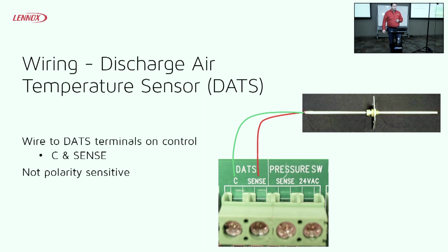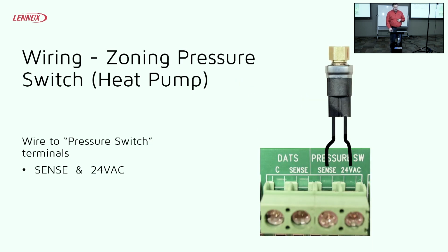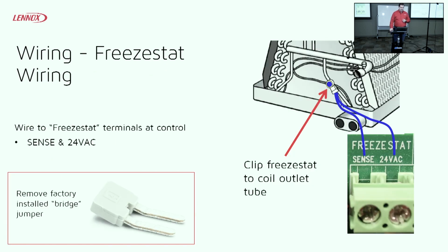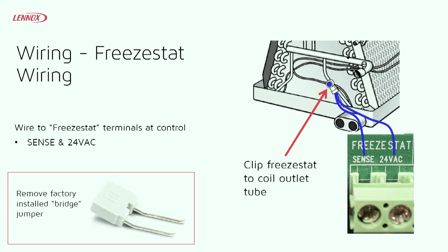Discharge air temperature sensor, again, just wire straight to the zone board. It's just a basic thermistor, so it doesn't matter. You can switch those wires any way you want. Heat pump pressure switch, again, that's going to wire back to that zone board with the pressure SW terminals. And then your freezestat will have this little bridge installed there from the factory. So if you do end up having a field installed freezestat, you just take that out, pop your freezestat in. Piece of cake. Questions about that so far? Yes, sir.